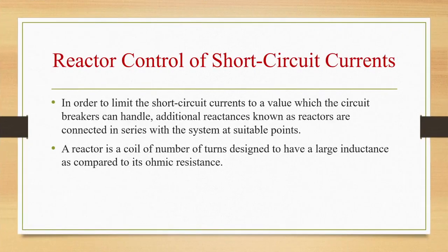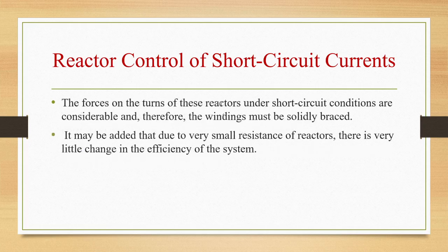So in order to limit the short circuit current to a value which the circuit breakers can handle, additional reactances known as reactors are connected in series with the system at suitable points. What is a reactor? A reactor is a coil of a number of turns designed to have a large inductance as compared to its ohmic resistance.